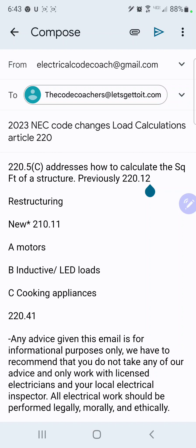For dwelling units, you have to count the garage, and the floor area shall not include open porches or unfinished areas not adaptable for future use as habitable rooms or occupiable spaces. The old language read: you would not include open porches, garages, or unused or unfinished spaces not adaptable for future use. Now it reads: not adaptable for future use as habitable rooms or occupiable spaces — which leaves some interpretation between you and your inspector. To recap: you do have to count garages in your square foot general VAs when calculating dwelling units.